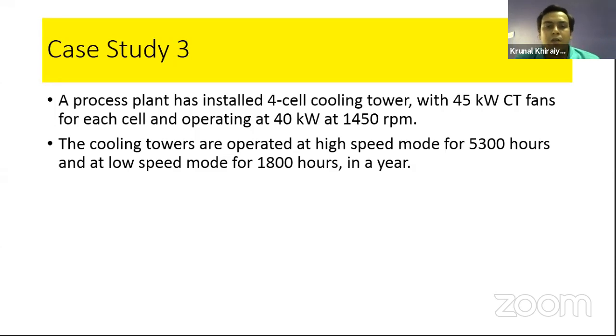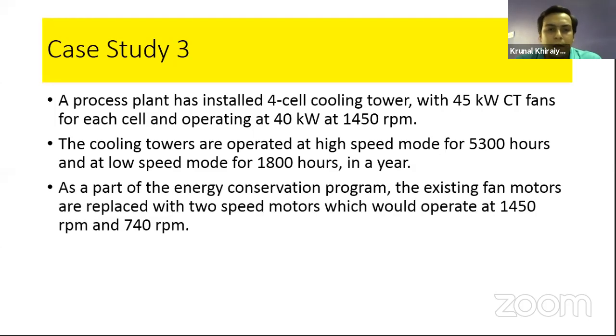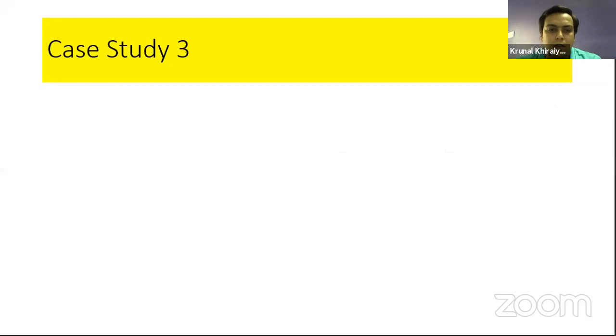It means the load on the cooling utilities varies according to the requirement of the process. Sometimes it requires running at high speed, sometimes at low speed. So the bifurcation of running at high speed and low speed is given here, measured in real conditions. As a part of the energy conservation program, the existing fan motor is replaced with 2-step motors. In the first case, we have only a single motor running at constant RPM. In the second, through the energy audit, we suggest that you use a VSD, or you can use two different speed steps for the motor. So we have these two types of case.